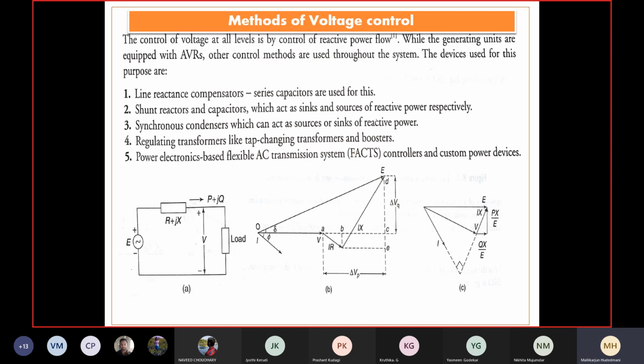Therefore, in that perspective, there are different identifications. With those different identifications, different methods are incorporated to supply the required reactive power to the system, so that the system voltage becomes better and within the permissible range. The first and foremost mechanism is line reactance compensators. As we are very sure, a power system incorporates various types of generators, transmission mechanisms, transformers, switchgear and loads. Definitely, to deliver the power to the end user, transmission mechanisms, cables, etc. are very necessary and essential.